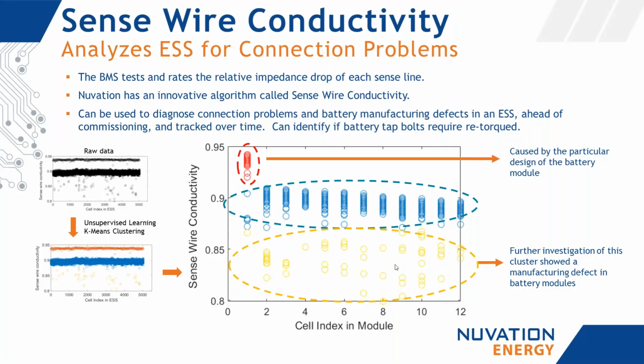Everything was good. But what's fascinating is that by looking at data and analysis, we were able to detect this manufacturing defect ahead of commissioning. Had we not done that, it would have resulted in those cells running a bit warmer and aging faster. This same sort of data could be tracked over time, and one could actually identify, for example, if due to thermal cycling your battery cells need to go in and get retorqued.